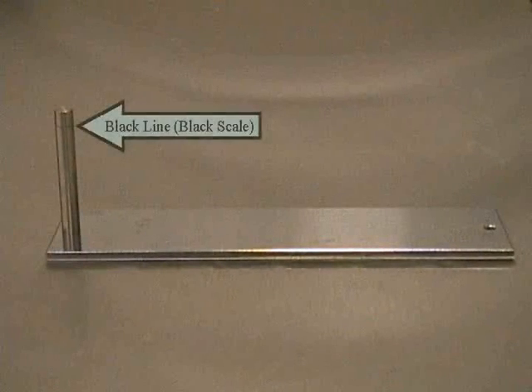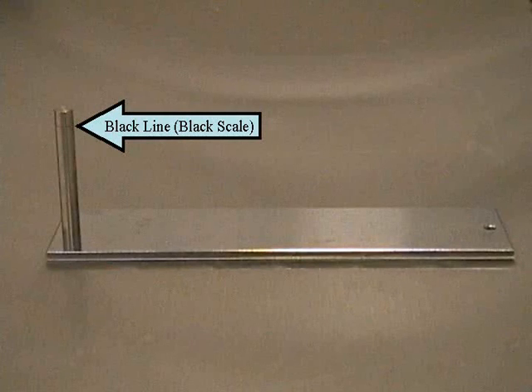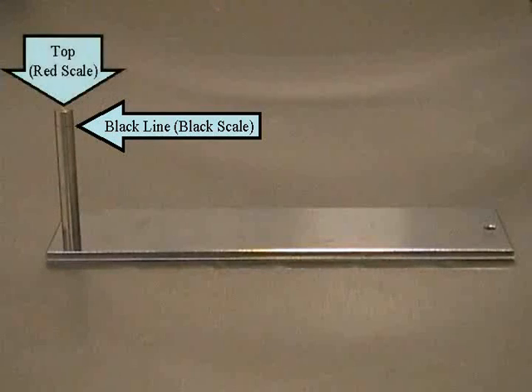We want to use our height gauge to make sure that the height of the mounted sample is leveled in one of two ways. The first way is to use the black line on the gauge. This indicates that you will use the black scale on the Z-axis. The second way is to align our mounted sample with the top of the height gauge. This indicates that you will use the red scale on the Z-axis. These two scales are used for setting your working distance. Later in this video, we will show the scales on the Z-axis.